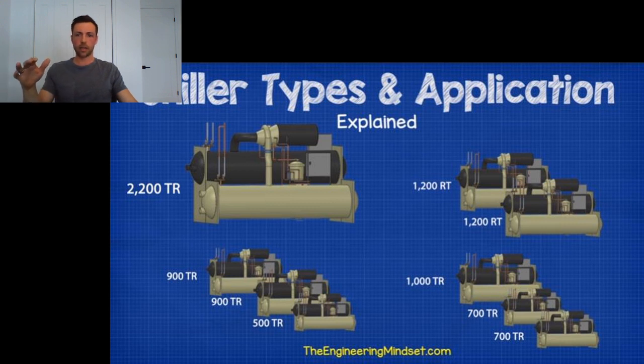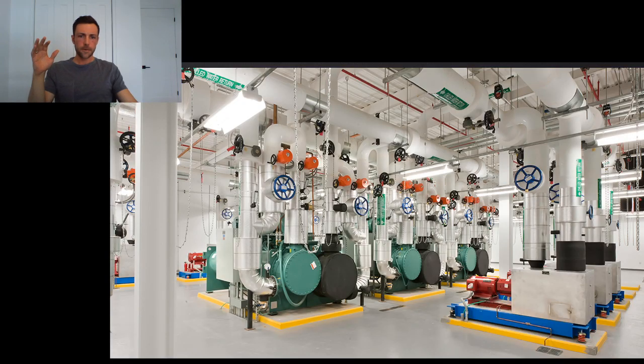Also, finally, the other thing is that because these equipment are critical to some operations, there is often what is called system redundancy, meaning that if you need 2 chillers for your cooling load, well, you're gonna add a third one just in case. If one fails, then you got a backup one, and you can maintain your operations, whether it's cooling your data servers, having your facility continue making food if you need it, etc. So this also makes the inspection process much simplified, as they can be inspected all year long instead of waiting just the winter when they're off.